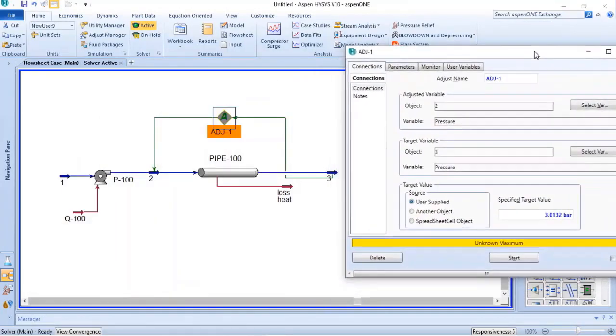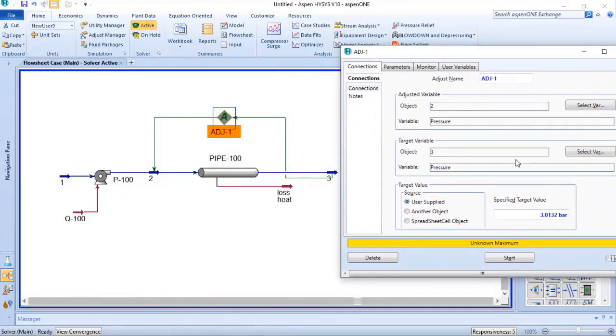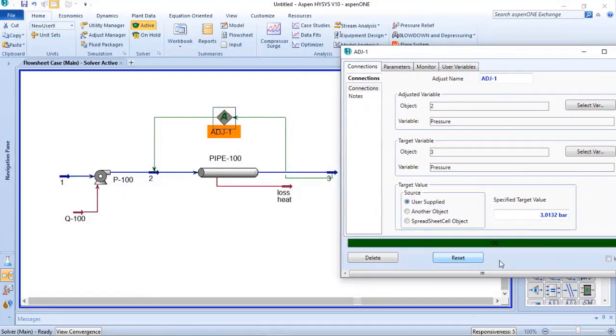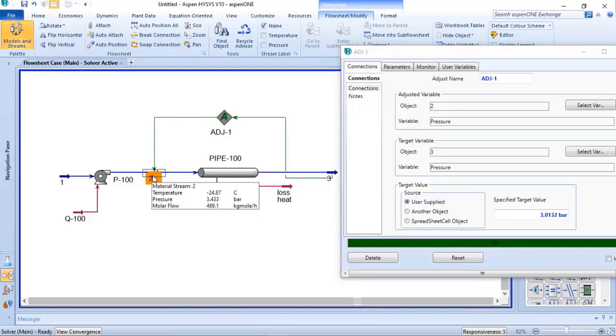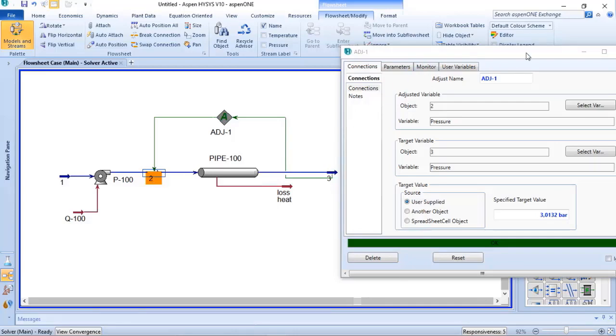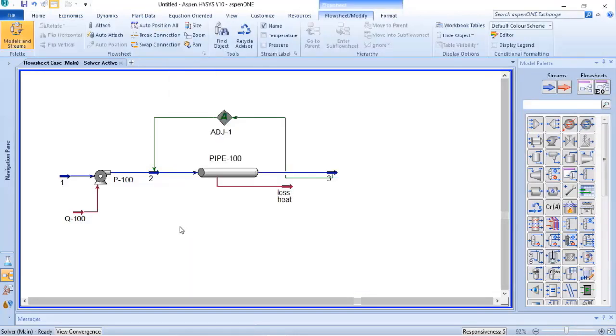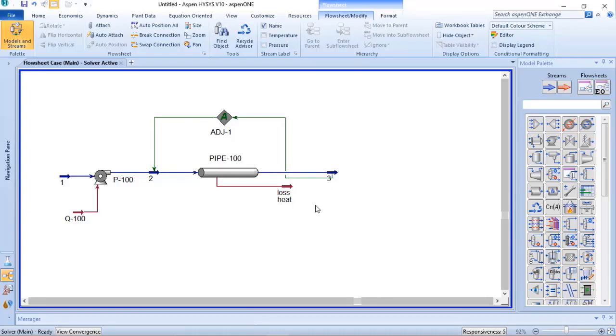And now we have the convergence of the adjust. And when I return here, you can see now that the pressure at the discharge of the pump is higher than 2 bar, and it is because we have the pressure drop between stream 2 and stream 3. And with this, we were able to define the minimal pump discharge pressure to reach 2 bar g at the outlet of the pipeline.